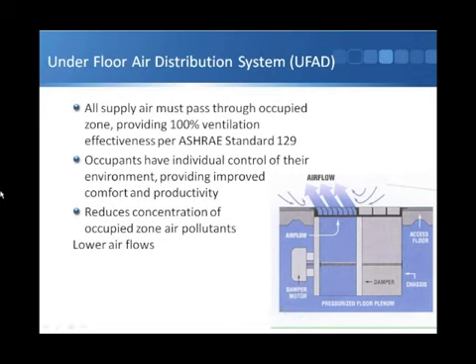And in fact, ASHRAE is rewriting its underfloor air distribution guide at this point in time. They have been quite successful, though there have been issues to do with air leakage in the plenums, and that's one of the points that ASHRAE is dealing with in the guide revision. Those kinds of issues have been to do with how well sealed the plenum is, and interesting aspects.